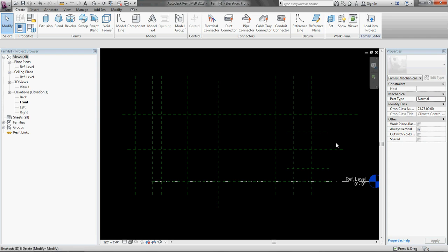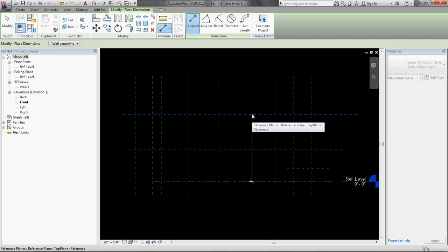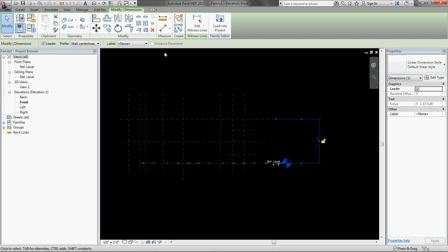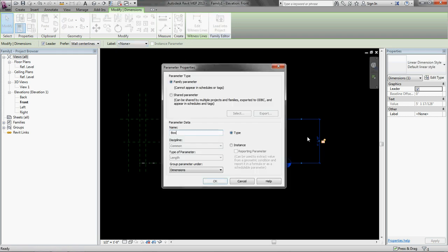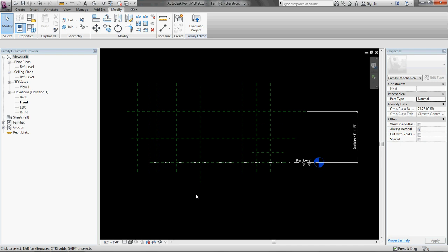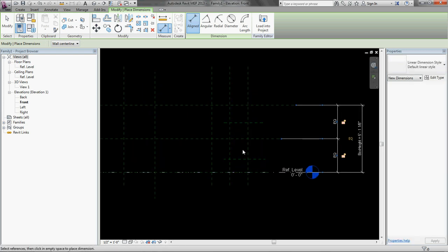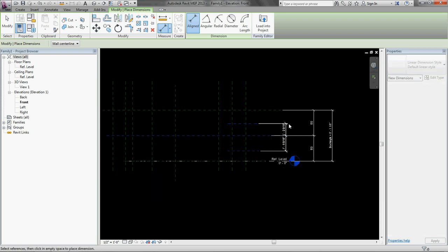Okay, dimensions, DI. We're going to set the height of the box. Box height. And then the center line, since I want it to be the true center line, I'm just going to set it equal. And now these two pipe connections. If I was working off a cut sheet, I would look that up and set them to whatever they are based on the cut sheet. But again, this is a generic family, so I'm just going to make it simple on myself. I'm going to set them equidistant, symmetrical, around the center line, if Revit will let me do that.